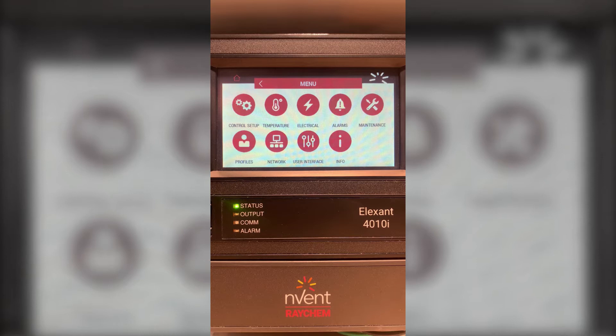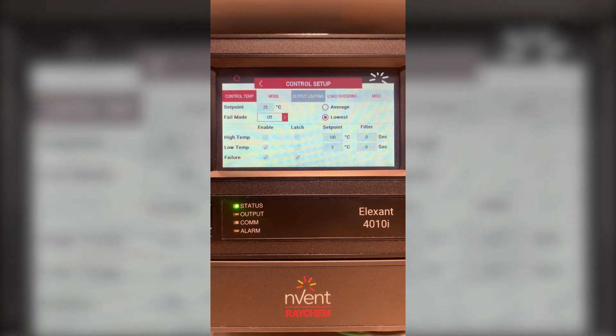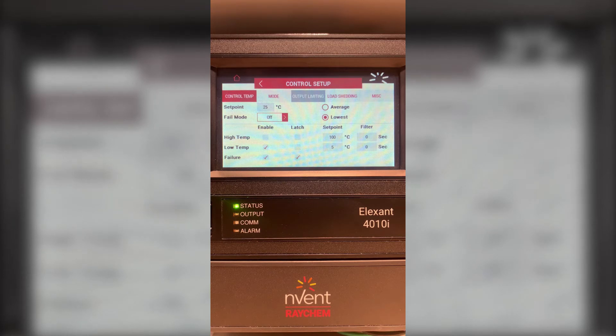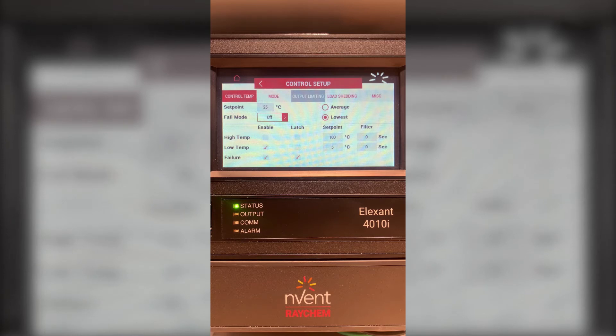Going back to the main menu I'll choose control setup. In control setup you'll have your set point, which is also your maintain temperature, the fail safe mode which can be fail on or fail off, as well as your high temperature, low temperature, and failure alarms. These can be enabled or disabled and latching and non-latching. Also you can select to have your RTDs control on the lowest temperature or the average of your RTDs should you have multiple RTDs.